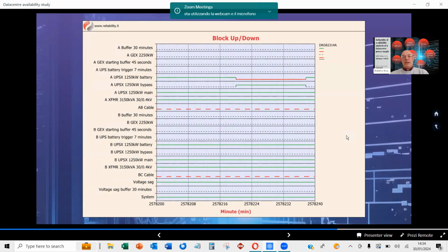Same but different characteristics here. We got the UPS battery down, we got the UPS bypass goes up. In the meantime, we put out of action, we set fire to 2 cables, the AB cable. These are the medium voltage cables going from unit A to unit B. And also we set fire to the cable going from unit B to unit C. So in other words, unit B is completely unpowered, and it has to rely on the generator.